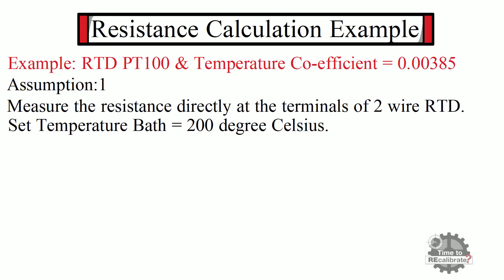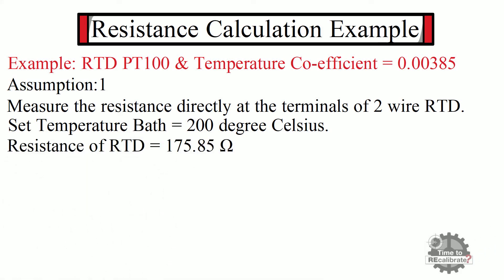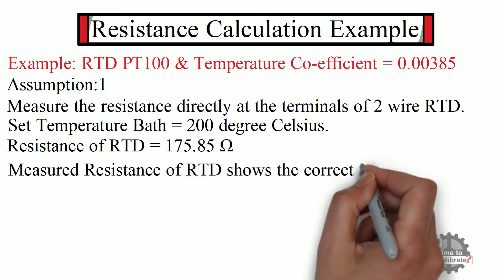And measure the resistance of RTD at its terminals. You should get 175.85 ohm resistance, which is correct measurement. In other words, the measured resistance of RTD shows the correct temperature reading.